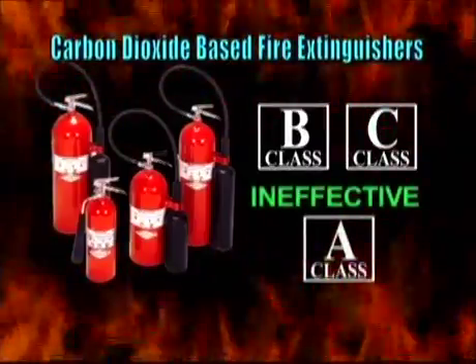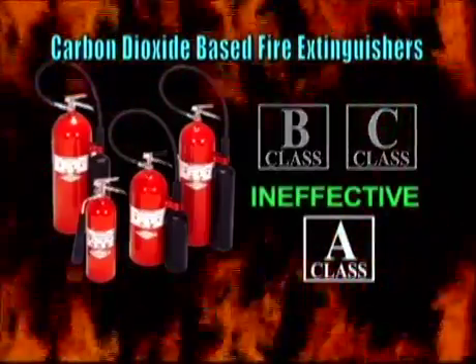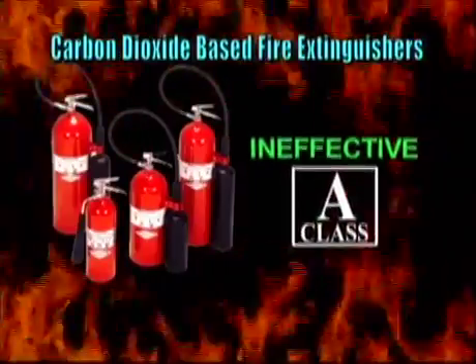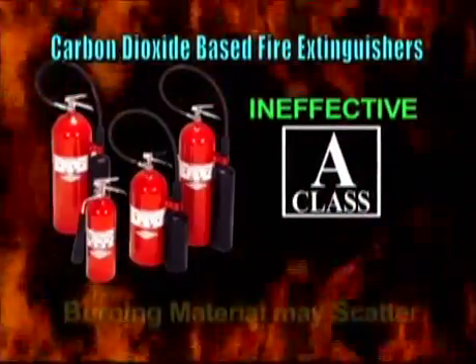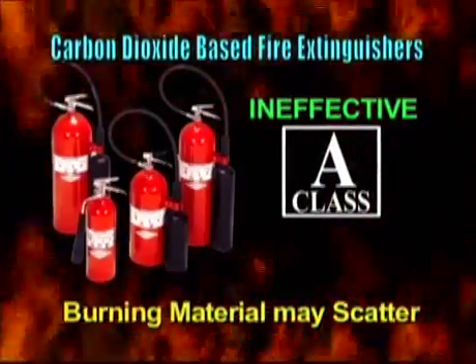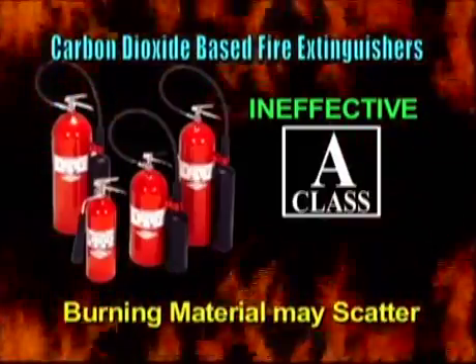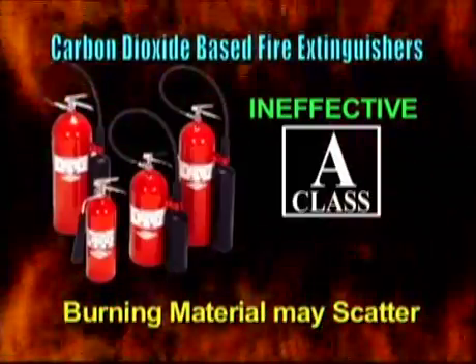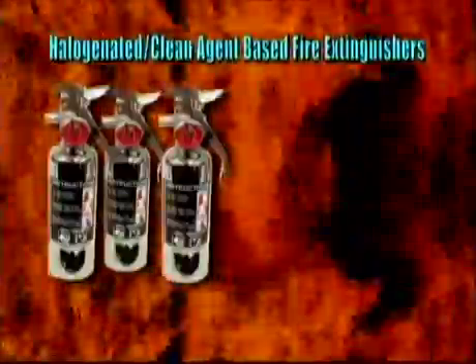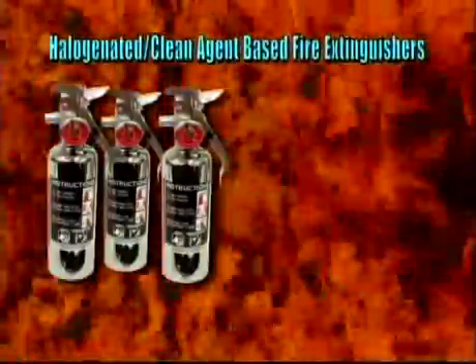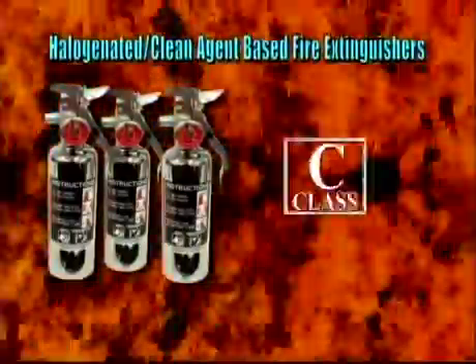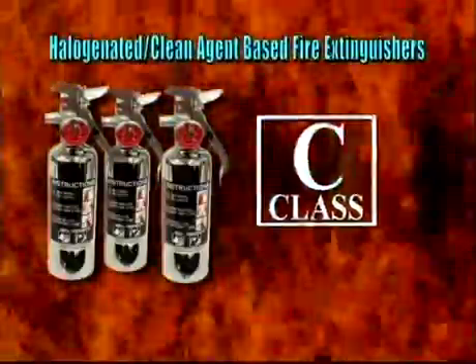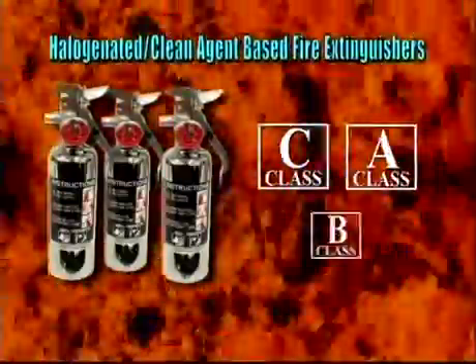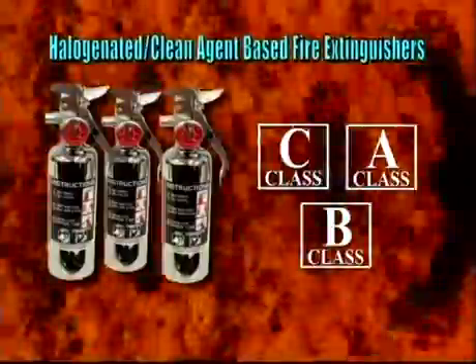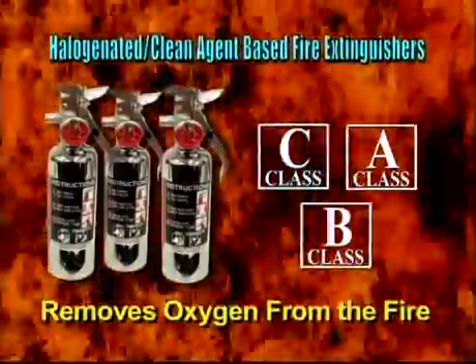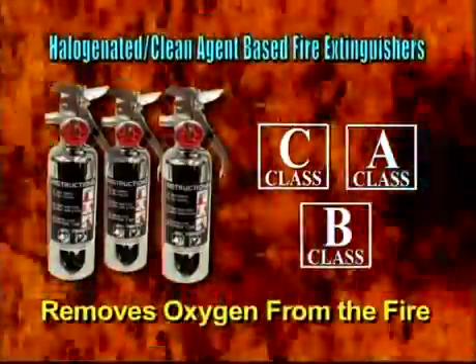They are ineffective on Class A fires because the fire can continue to smolder and possibly reignite. Also, the high-pressure discharge can cause the burning materials to scatter with a Class A fire. Halogenated or clean agent-based extinguishers are to be used mainly on Class C fires, but can also be used on Class A and B fires as well. These types of extinguishers also remove the oxygen from the fire.